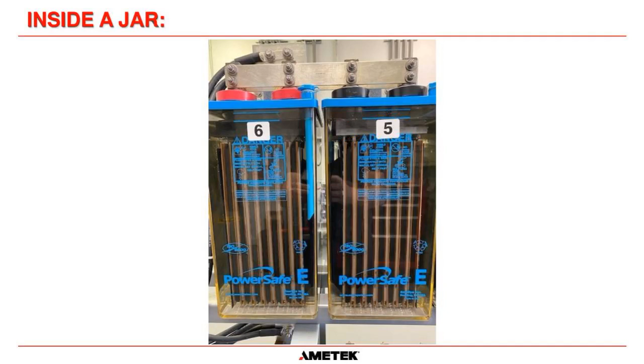With a vented lead acid battery, you want to keep the electrolyte level somewhere between these two lines. I wouldn't get obsessive about it - it's okay to let the electrolyte level get to the low level line, because as long as we don't expose the plates, we're going to be okay. If it does get to the lower level line, put it in your maintenance system to top it up as soon as possible, but you don't have to panic about it.